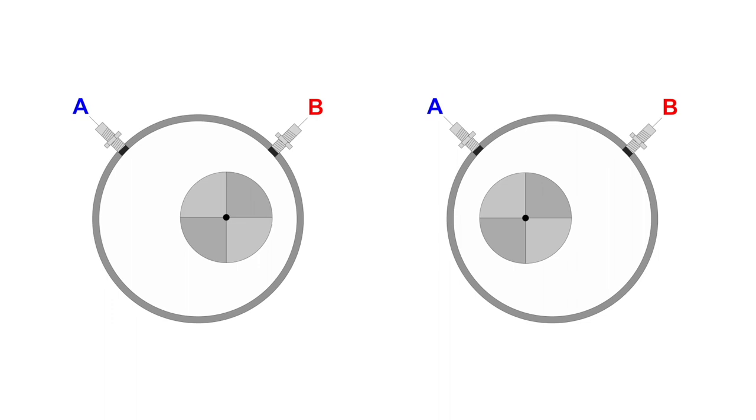The center line is the measurement of shaft position during run-up. We use the run-up module in the analyzer. We need to set the trigger properties. The run-up measurement is the series of individual readings. Each reading must be triggered.